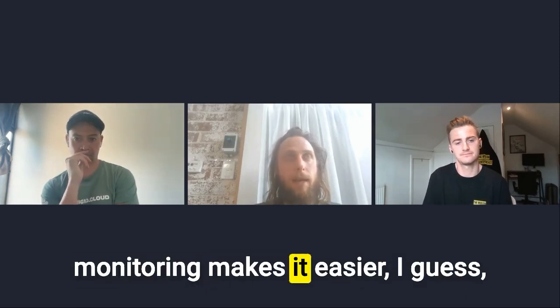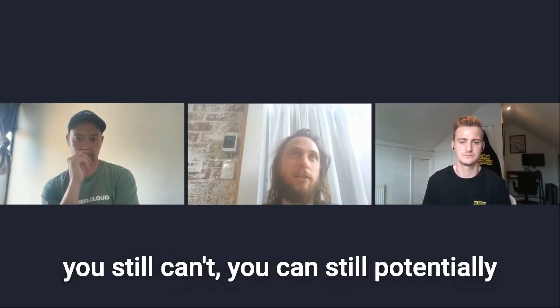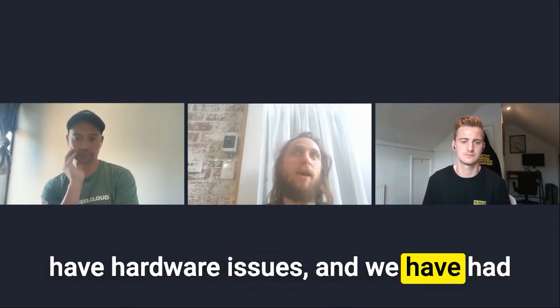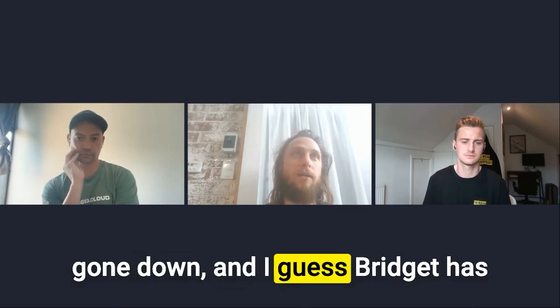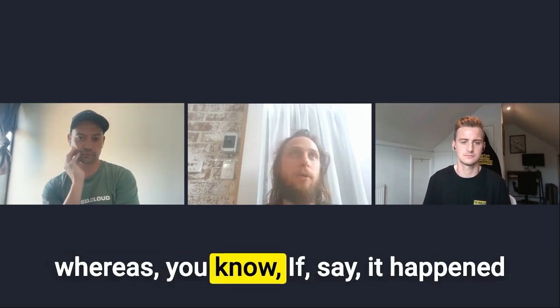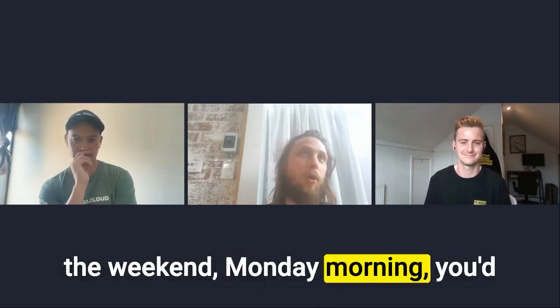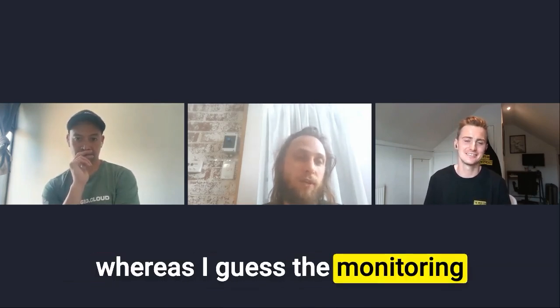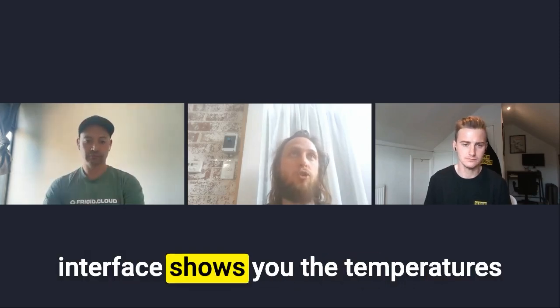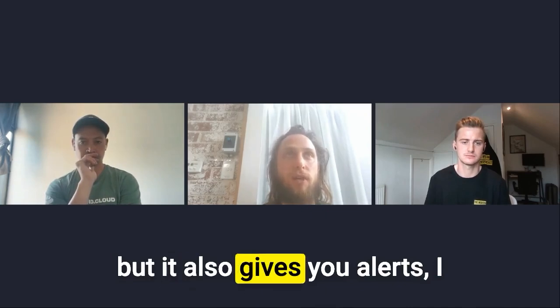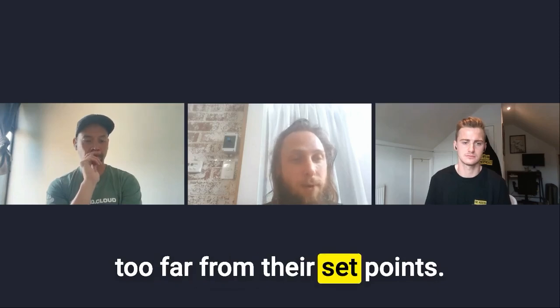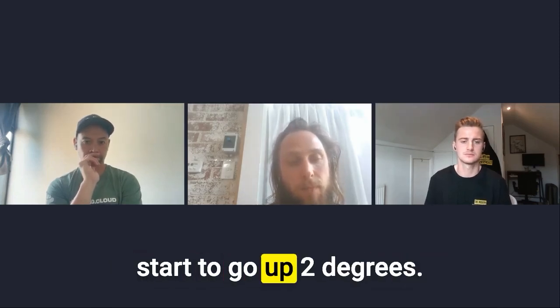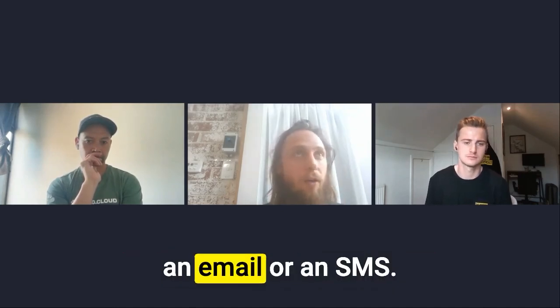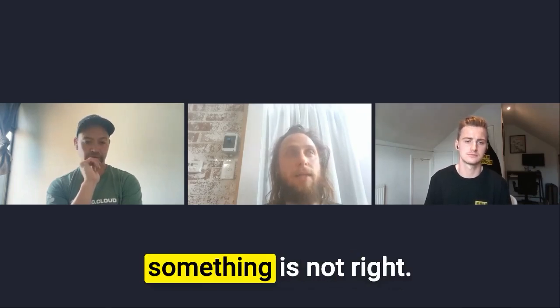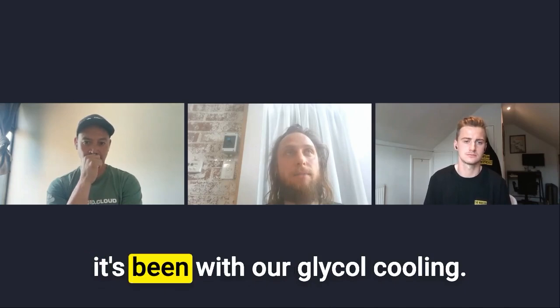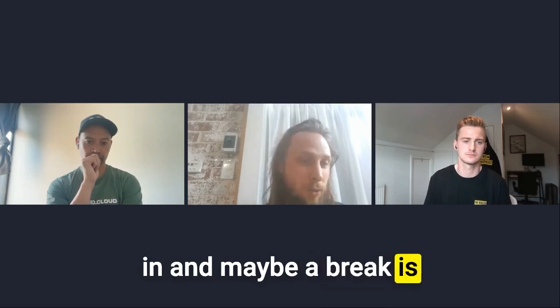Monitoring makes it easier, I guess, because you can still potentially have hardware issues. We've had a few issues where our glycol unit's gone down, and the app has actually alerted us to that. Whereas if it happened on a Friday night and we went home for the weekend, Monday morning you'd come in and everything would be hot. The monitoring control interface shows you the temperatures on screen, but it also gives you alerts if any tanks drift too far from their set points. If one that's cooling starts to go up 2 degrees, it sends us an alert, either an email or an SMS, letting us know something isn't right. Each time that's happened, it's been with our glycol cooling, so we've had to come in and maybe reset a breaker or something like that.